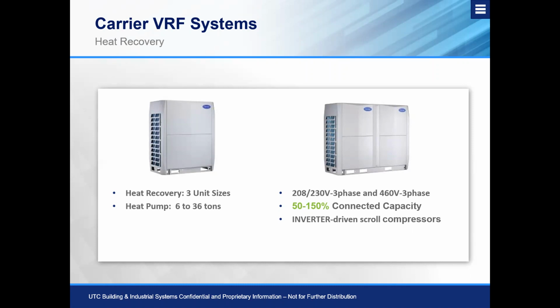Now, the heat pump will range from 6 to 36 tons, and the heat recovery will have 3 different unit sizes: a small, medium, and large cabinet. These are available in 208/230 volt 3-phase and 460 volt 3-phase, and they'll range from a 50% minimum to 150% maximum connected capacity ratio. Okay, and these utilize our inverter-driven scroll compressors, unlike the Toshiba Carrier systems, which use the rotary style compressors.